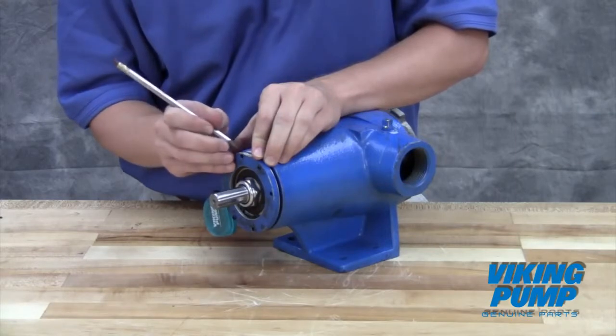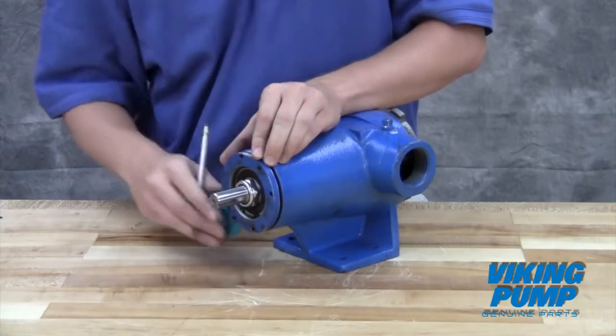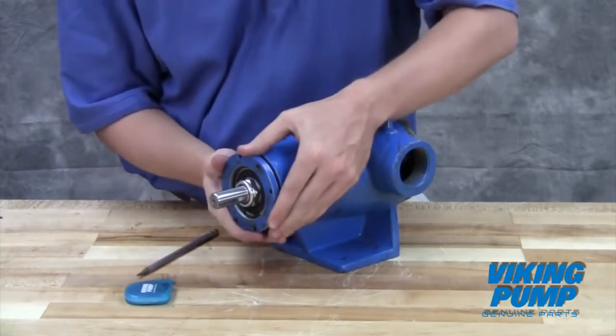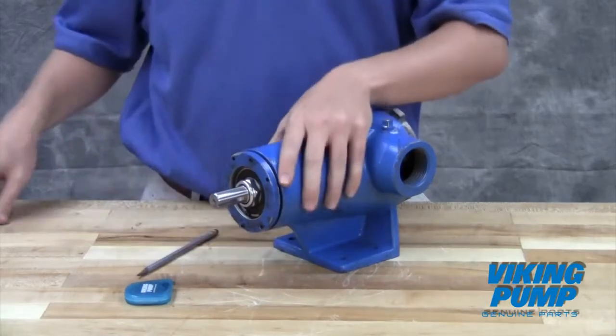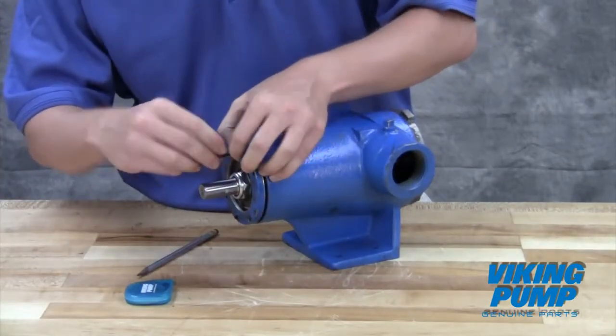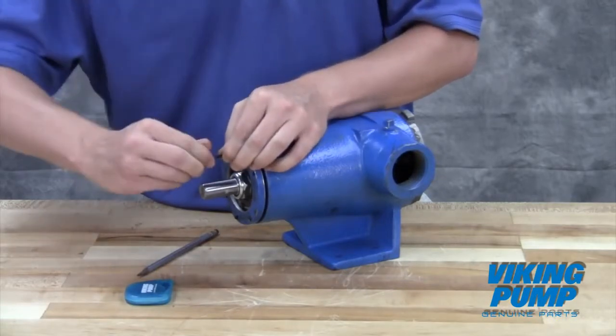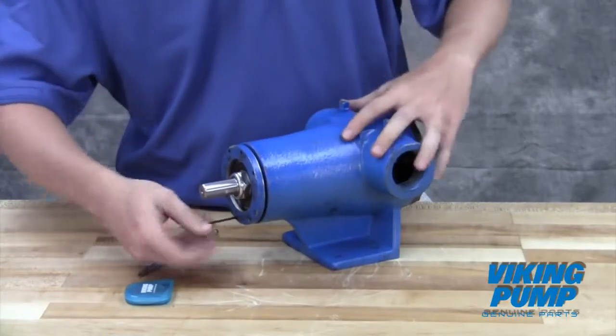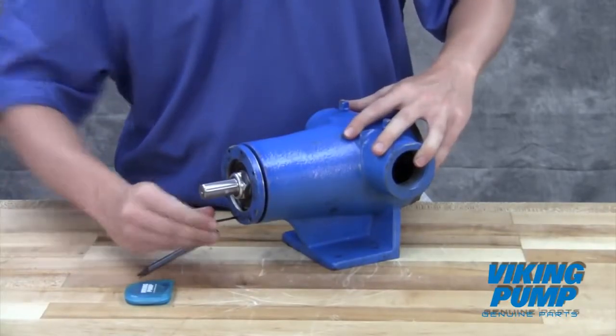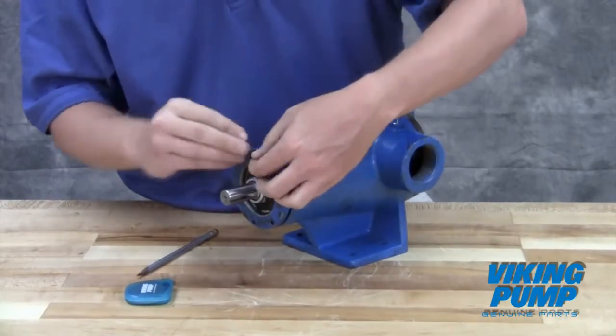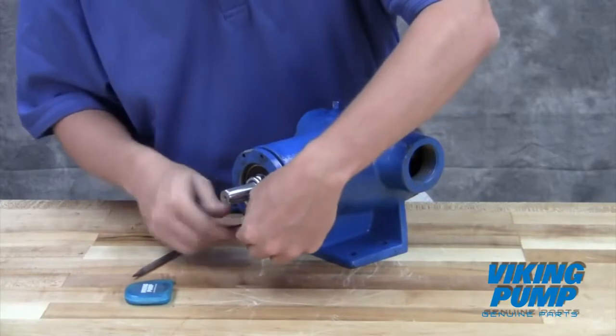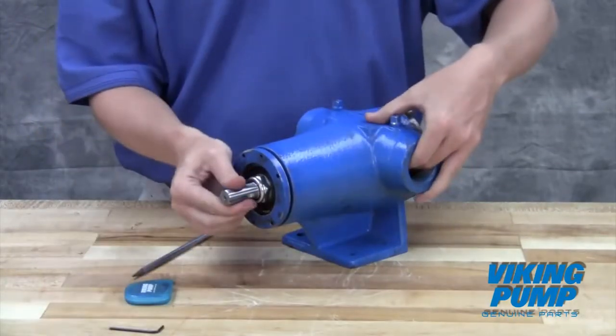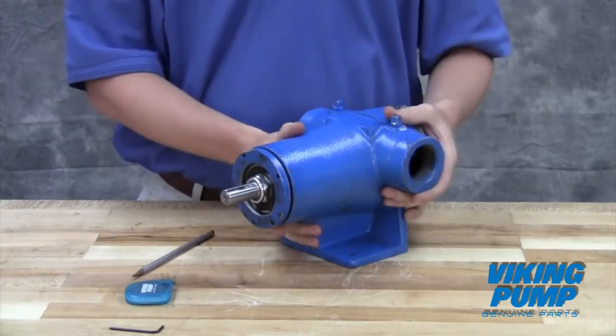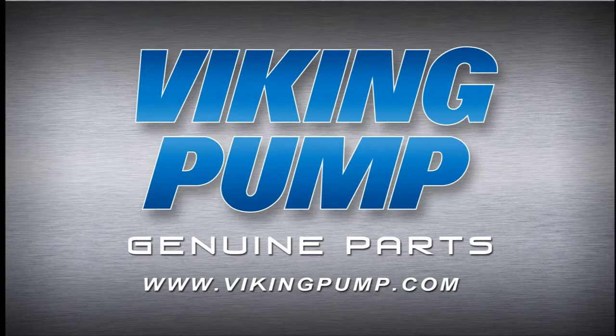Make a second mark on the casing left of the first mark at a distance indicated by the technical service manual. Rotate the thrust bearing assembly counterclockwise until the bearing housing mark aligns with the new casing mark. Lock the set screws in place to hold this setting. Your Viking Pump high-speed compact internal gear pump is now fully repaired and ready to put back into service.